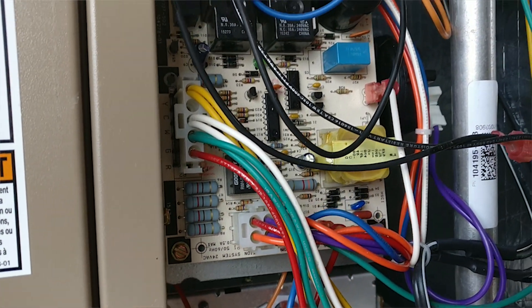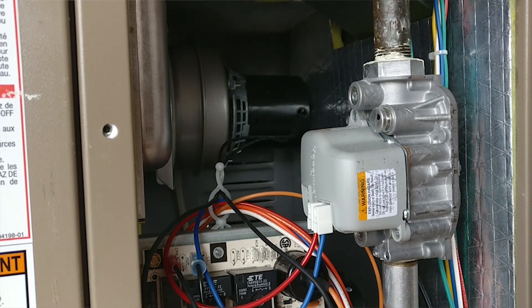A gas-fired furnace compared to a space heater is incredibly complex. It requires a sophisticated control system to monitor and regulate gas flow and ignite the flames upon startup, an expensive heat exchanger to combust the gas safely and get the exhaust away from the living space, and multiple fans and motors to expel exhaust and move air throughout the furnace. But putting up with all this makes far more sense in cold climates than using electric heat. Although electric heat itself is 100% efficient, electric power generation is nowhere near that amount. So long as we continue to use fossil fuels to generate electricity, using the fossil fuel itself to heat makes far more sense.